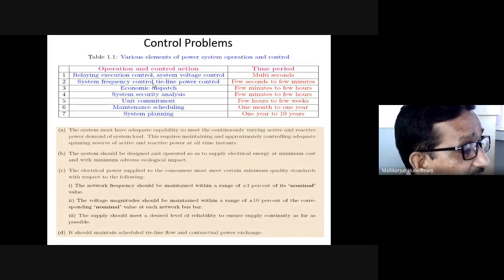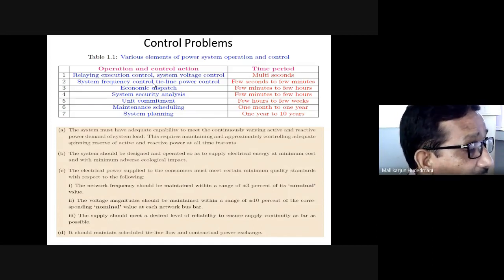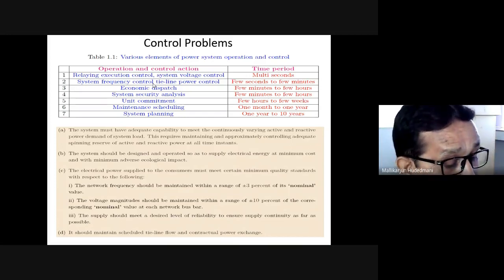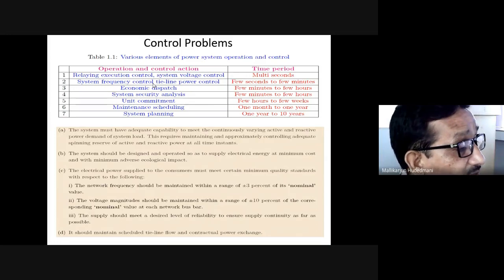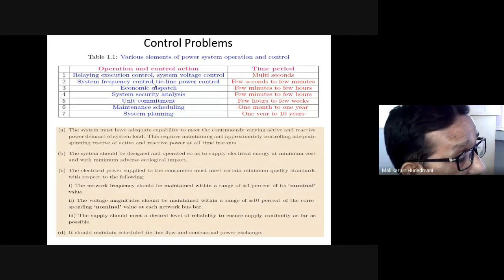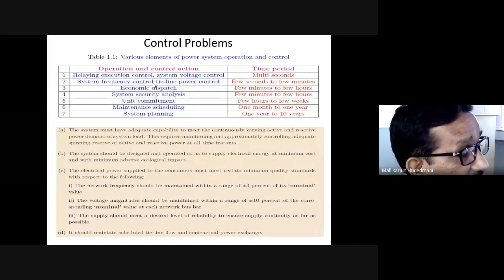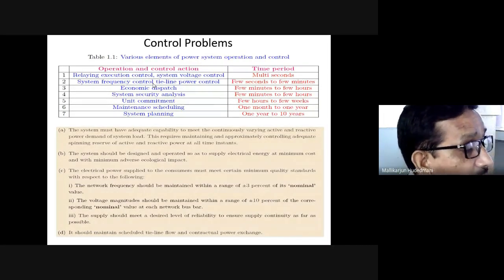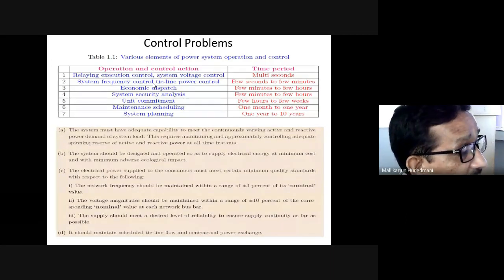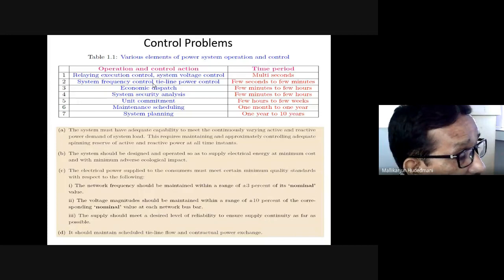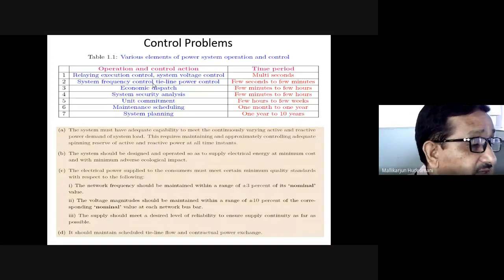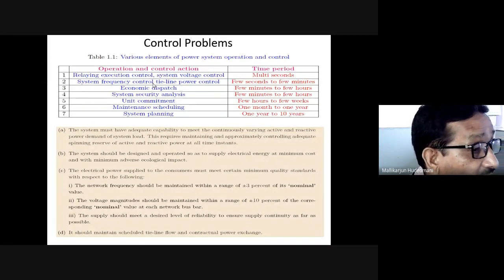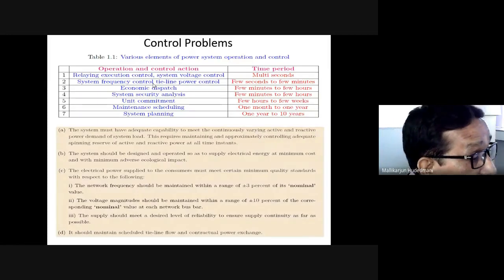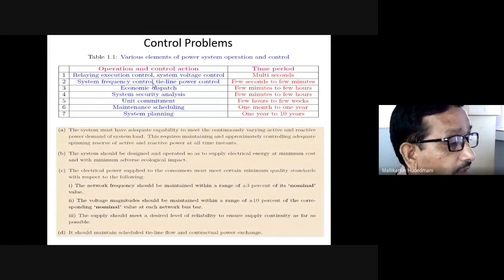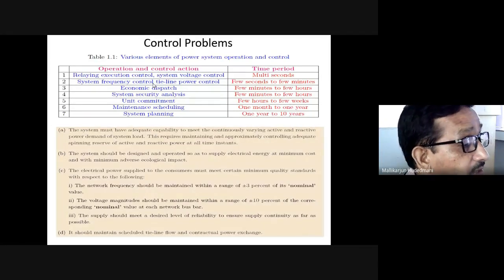Then the system was very healthy before the drawal of power from Karnataka State. Assume that there was a fault, a disturbance in the Karnataka State transmission grid. Then the system frequency, which was supposed to be at 50 Hz plus or minus, is not within the range. This pulsation, this change in frequency, not only affects the Karnataka State grid, but the power which is being pumped towards the Tamil Nadu grid, for which they are purchasing the power for their need, also gets injected with the fault. Therefore, that frequency deviation propagates to the healthy system, which is the borrower. So their system also gets affected because of the deviation in the frequency.